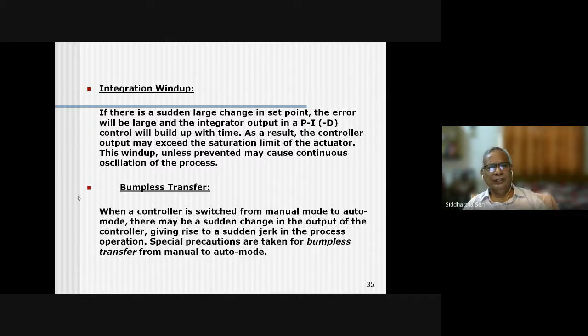Another is the bumpless transfer. When a controller is switched from manual mode to auto mode, there may be a sudden change in the output of the controller, giving rise to a sudden jerk in the process operation, and special precautions are to be taken for bumpless transfer. That means there is no jump or bump in the manual to auto mode transfer, because often we require to operate it in manual mode, then transfer to auto mode. This transfer often causes a big jerk in the output.